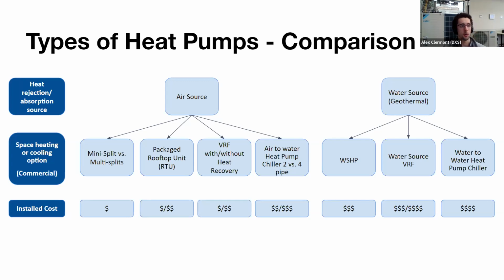Staying on the air source side, you can also go VRF, where again the cost is a little bit dependent on what you're doing. Is it a heat pump system? Is it a heat recovery system? What type of indoor units are you using? That will all change the cost profile of that solution a little bit. Next on the air source side, if you do air to water heat pumps, whether that's 2-pipe or 4-pipe, that also changes the cost profile a little bit, depending on what it's serving or what exactly the machine is doing.